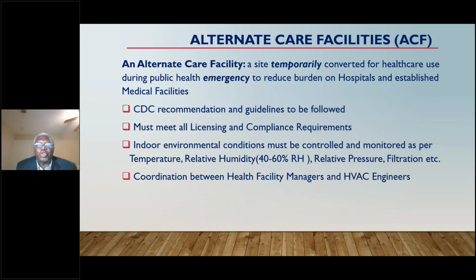Indoor environmental conditions must be controlled and monitored, including temperature, relative humidity at 40 to 60% RH which is now recommended, relative pressure, filtration system, and so on. Coordination between health facility managers and HVAC engineers is very, very key.